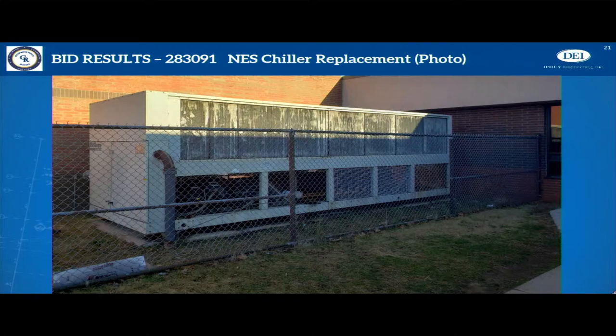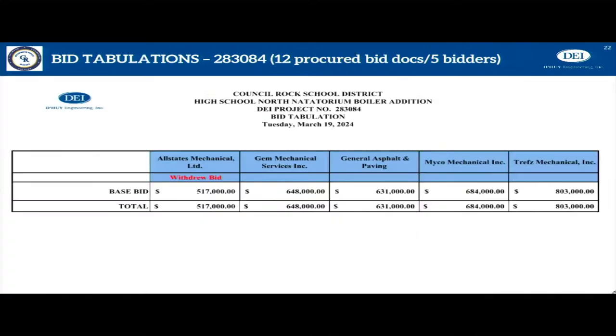There's a picture of the chiller. The new chiller will go in the same location, but this fencing will actually be moved slightly forward, closer to the sidewalk, because this chiller was tucked too tight against the building for an air-cooled unit. It needs space around it for air and ventilation to function properly, and this one is underneath the soffit and too close to the wall. So we pulled it out as part of the new design.